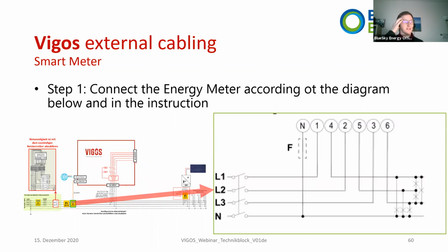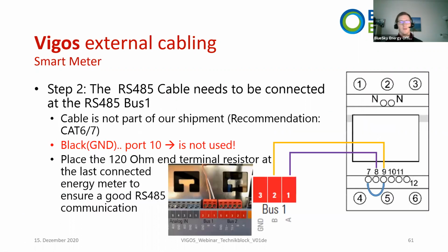The energy meter needs to be placed at the grid input point or output point, however you want to call it. But it's really important that the system is able to measure all the income power and the outcome power. And also the measurement direction is really important, so that you connect the grid to pin 1 and you connect your distribution panel to pin 4. So you can see in here, grid pin 1 and distribution panel pin 4.